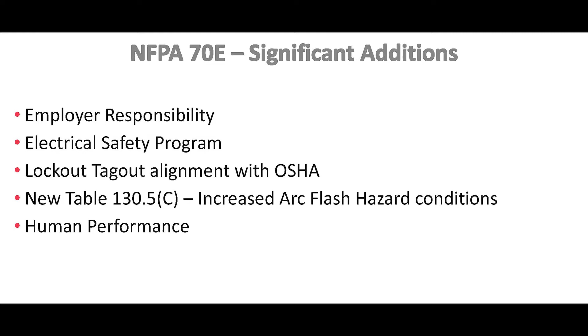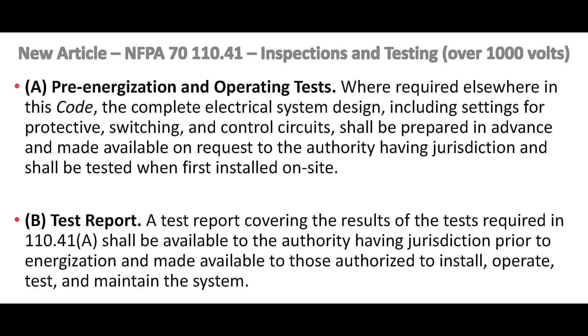Now, inspection. The electrical safety program shall include elements to verify new installations are inspected. You have to inspect new electrical installations, and it's got to be inspected by somebody that's qualified to do so. They added some service equipment. This is just labeling. You have to put labels on all your service entrances now. Marking, this is again reconditioned equipment. The electrical code allows you to use reconditioned equipment now. Again, pre-energization operating test. You have to inspect it before you energize new equipment. You got to document the test results on it, and those have to be made available to the authority having jurisdiction. There has to be a test report issued with it.